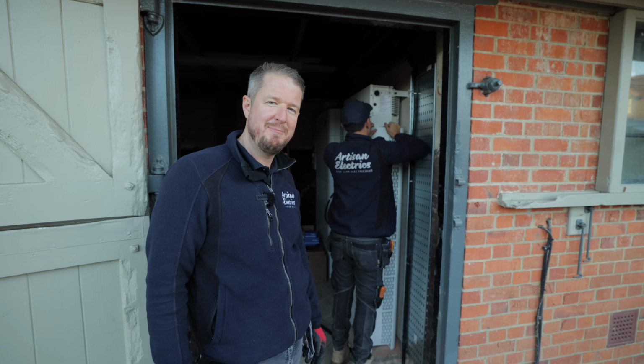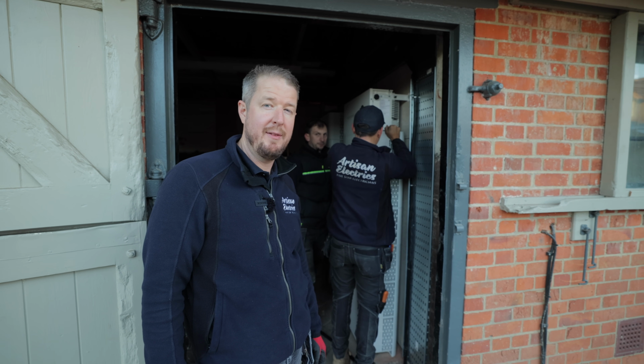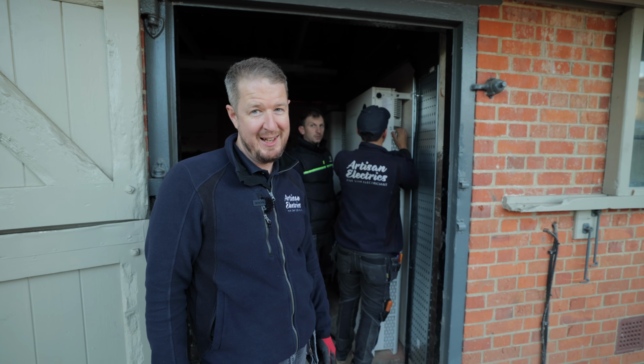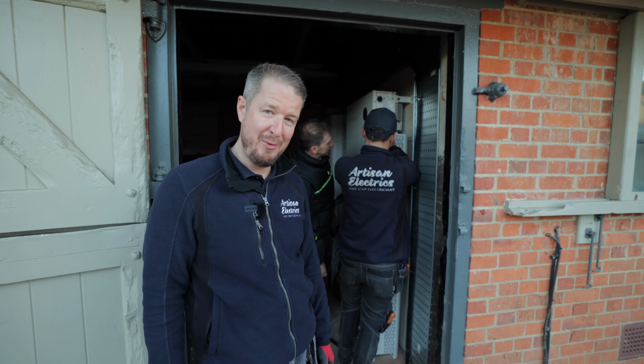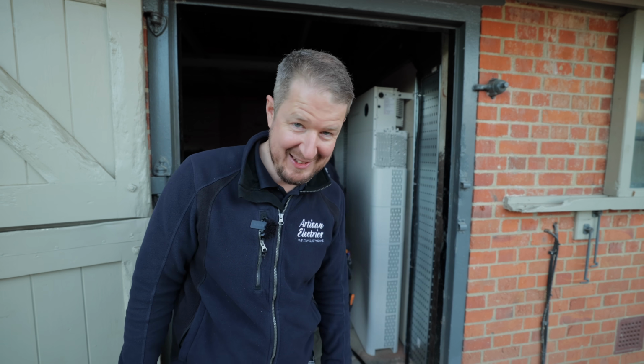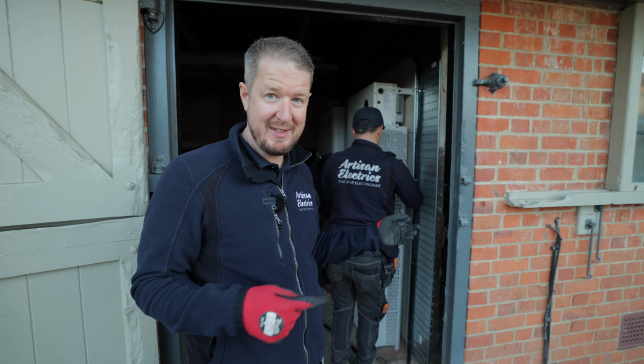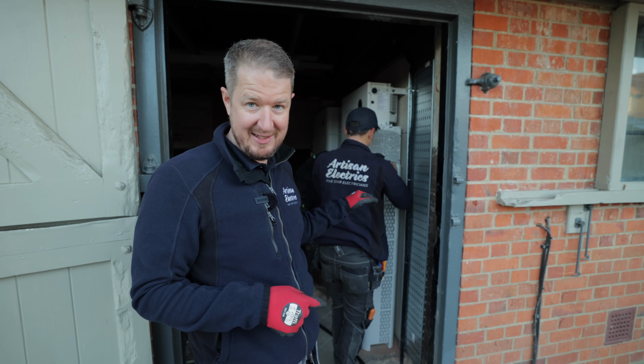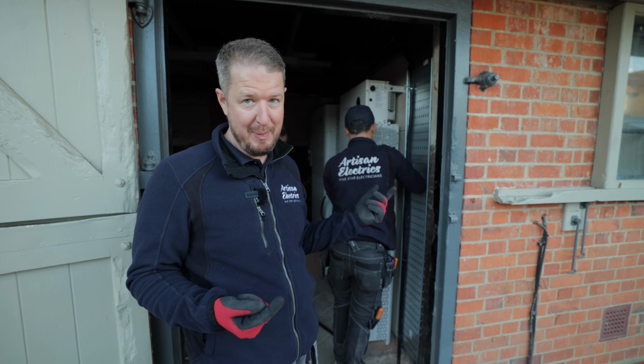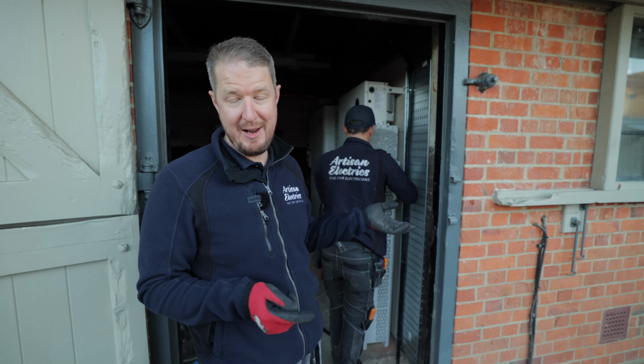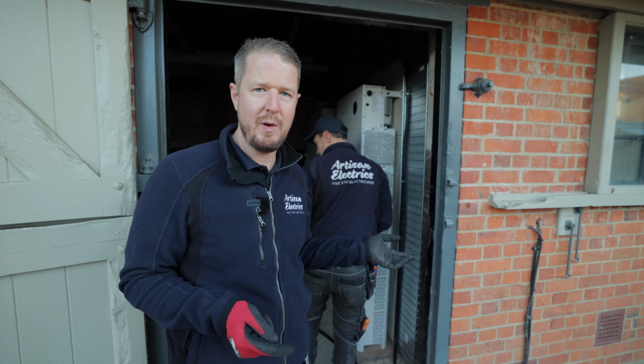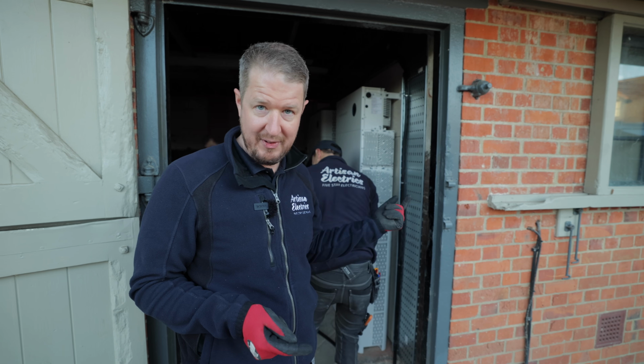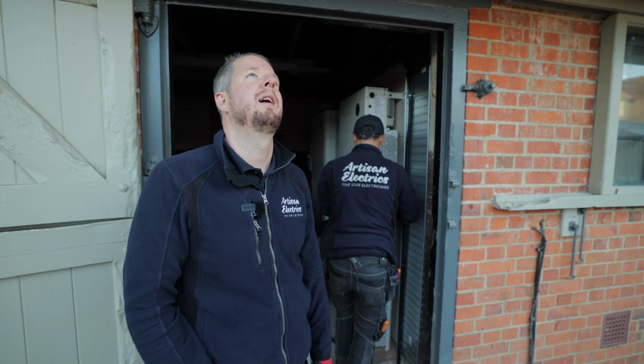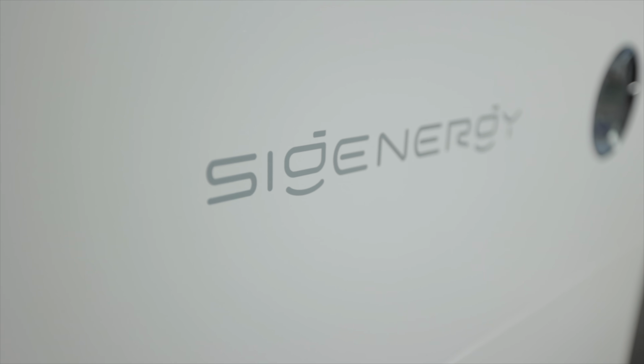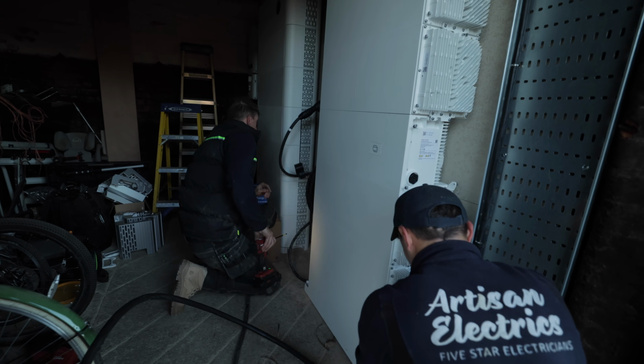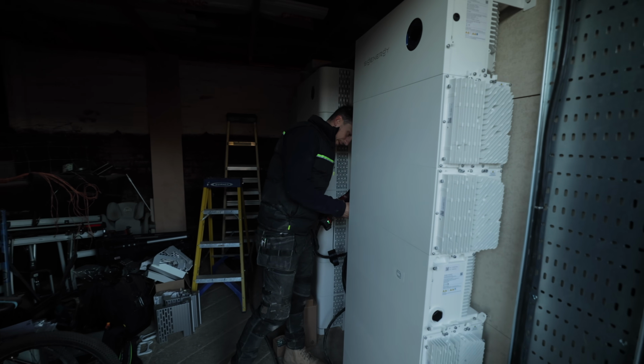Confession time. I know you guys think we're perfect, but we're not, we make mistakes, and here's another one to add to the list. The DC EV charging module, we stacked it in the middle of the stack. Luckily I posted an Instagram story last night showing what we were doing, and somebody told me Sigenergy said it needs to be at the top of the stack when they did theirs. So I contacted Sigenergy this morning to check, and they confirmed it needs to be below the energy controller, which is the top inverter module, just below that.